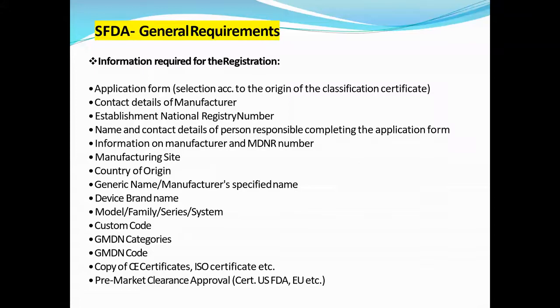Suppose you already have an existing CE certificate in Europe, then it becomes easy for you to enter the SFDA, Saudi Arabia. Even with the US FDA, if you have a 510(k), you can easily enter Saudi Arabia. Otherwise, if you are a newcomer, you have to register your firm and get your ISO certification done for your facility, make the technical file and give all the documents, fill up the application, establishment registration and your device details, generic name, country of origin. Suppose your country is India and the manufacturing site is Dubai, then you have to make note of it. So you have to mention those addresses with the details.